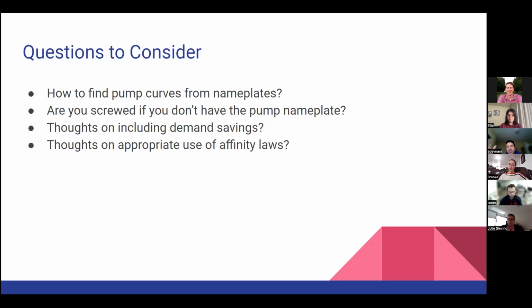So the general pump curve, like was shown in that slide, you'll get that, but you don't know exactly which line you're operating on. But the serial number will give that to you, and you had to call the manufacturer. And in our office, we've got a guy who is very comfortable and knows all the manufacturers, and we literally go to him nationwide, because let's say it's a Bell and Gossett pump that's in Florida, but if I get the serial number, I can call up the Bell and Gossett guy here and say, hey, for this model and serial number, can you pull out the curve?